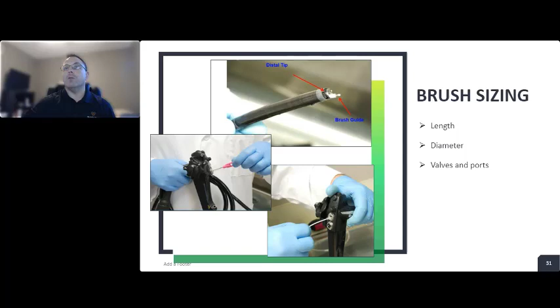You know, valves and ports, we see all kinds of different valve port brushes. I was in the repair industry for a little over 15 years. And one of the dirtiest areas we often see when these devices get taken apart is some of these valves and port areas, because we forget to put our brush into them, or we don't have a designated valve port brush to remind us to clean those. So we're just using the end of the scope brush to try and clean the valve and port. I would always recommend to people, look at a valve port brush for this, right?